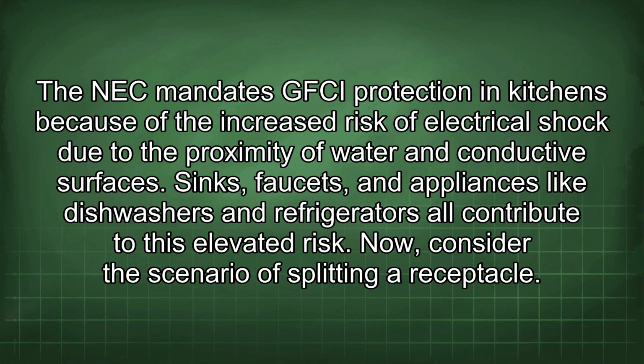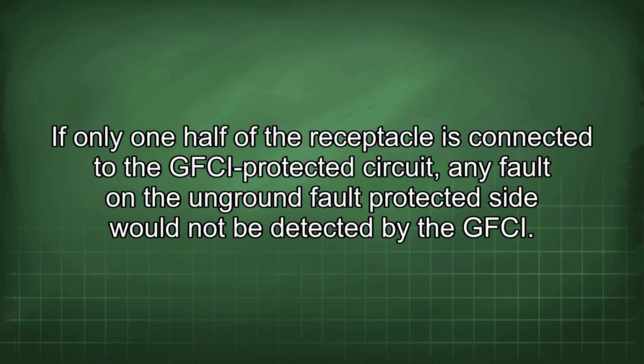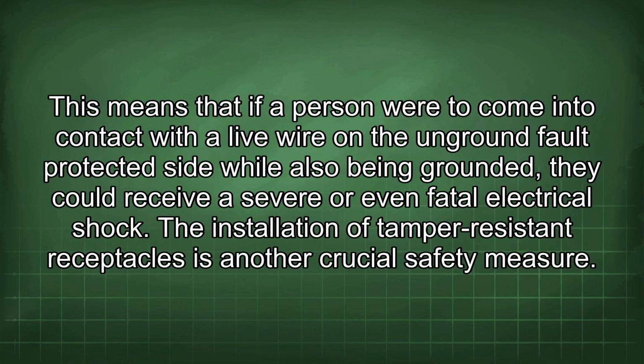Now, consider the scenario of splitting a receptacle. If only one half of the receptacle is connected to the GFCI protected circuit, any fault on the non-GFCI protected side would not be detected by the GFCI. This means that if a person were to come into contact with a live wire on the non-GFCI protected side while also being grounded, they could receive a severe or even fatal electrical shock.